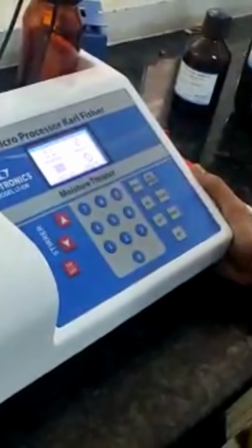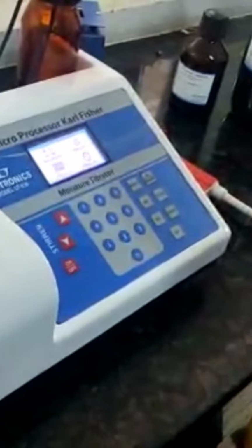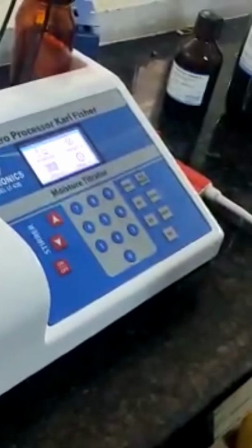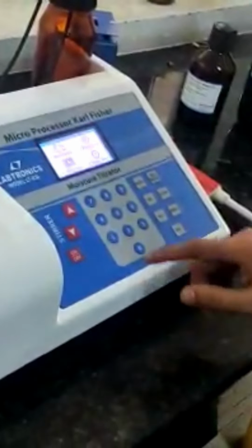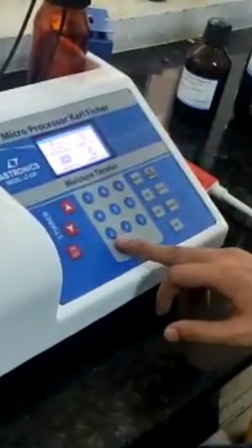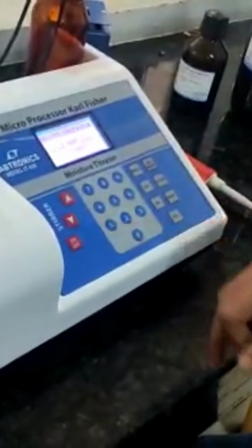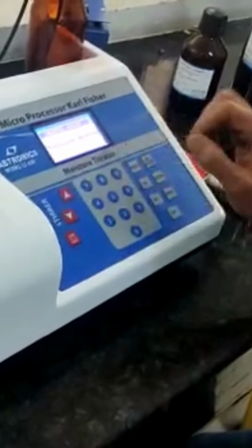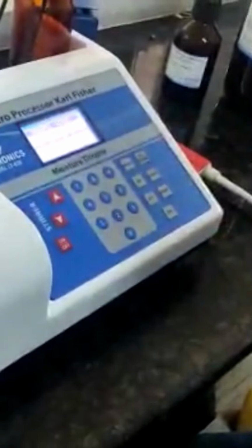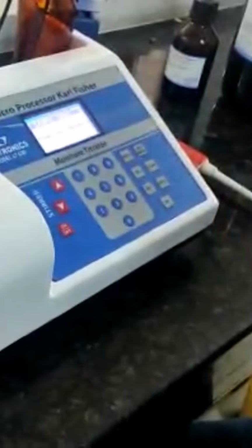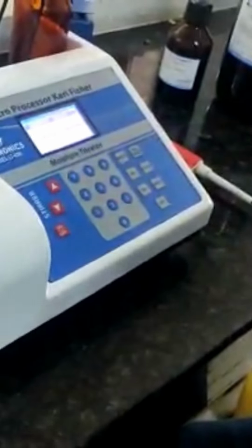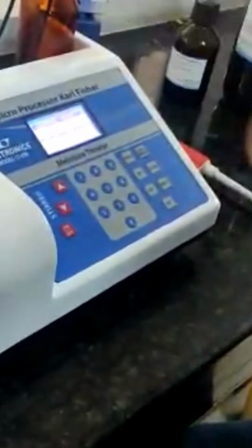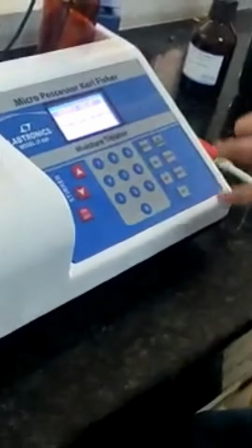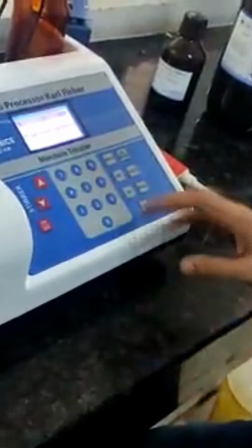And if you have liquid and you want to take the sample reading just by sample weight, then you have to select it like a solid sample. So suppose we have solid sample 1, then we have to put the weight of the sample. If the sample has more moisture, then you have to put less amount of sample. If the sample has less moisture, then you have to put more weight of sample. So this is the process that we have to follow.